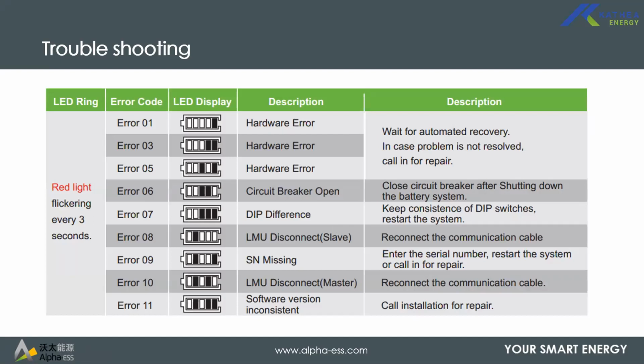So the battery has LED indications which show the battery status, in terms of, say, 20% graduation. When the battery has an error, the error indication is displayed on the battery status page. For different orientations of the battery, it displays a different error. As you can see here, I've got 11 errors. The outer ring that I mentioned earlier will be flashing green once every 10 seconds when the battery is communicating well. If it changes to red and it has only one bar, it means a hardware error.